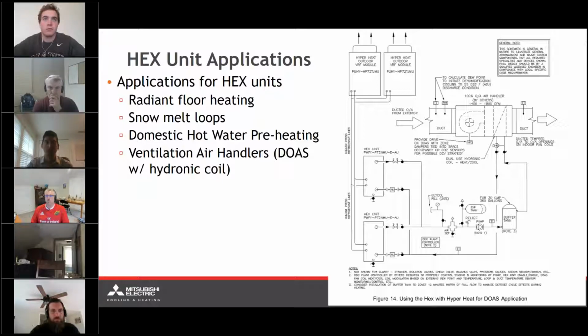So ultimately, we just need to make sure that for the hydronic air handler that's provided by others, we're sizing the coil appropriately. We're going to be sizing the HEX units that are delivering the water to that appropriately. And certainly we're going to want to make sure that we have a glycol for freeze protection, since this is a 100% outside air application, and most likely we're going to be running the water piping outdoors as well.